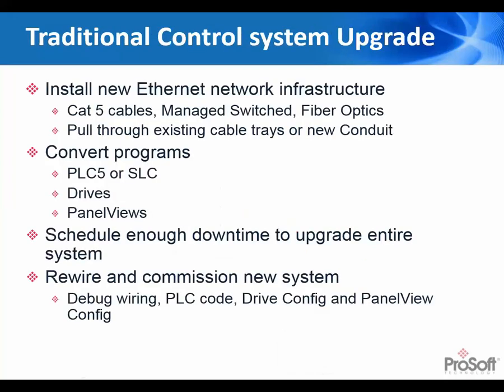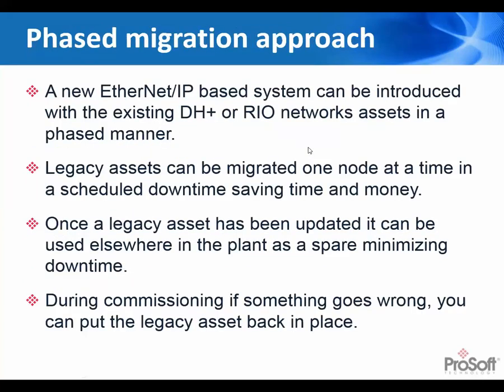So if we look at a traditional control system upgrade, a lot of those upgrades would be to install a new Ethernet network infrastructure, pull through Ethernet cables, convert programs, schedule downtimes for the entire upgrade of the entire system, rewire and commission system. But obviously, if something goes wrong, you've then got to debug the wiring, debug the PLC code, change the drive configuration and panel view configurations. So what could we do to change that more traditional approach? We can look at it from a sort of phased approach.